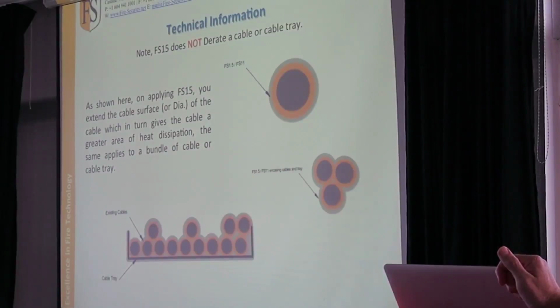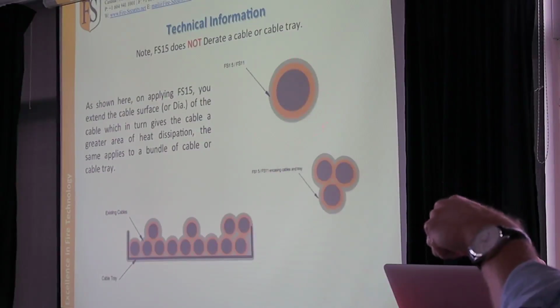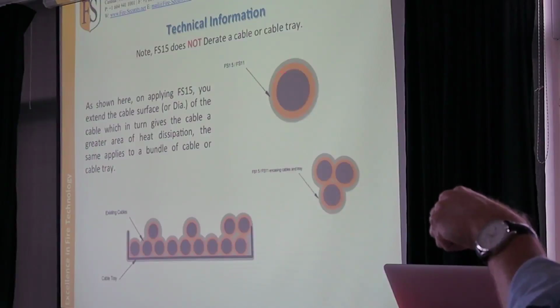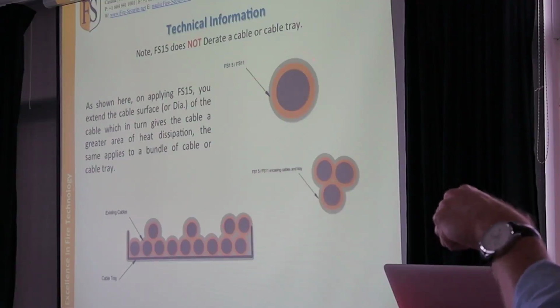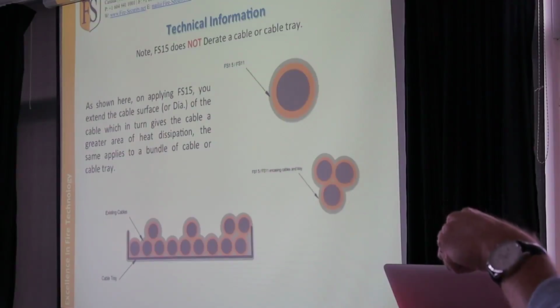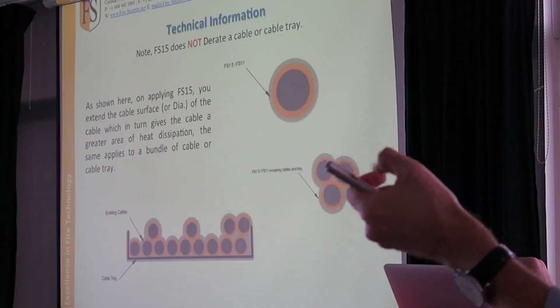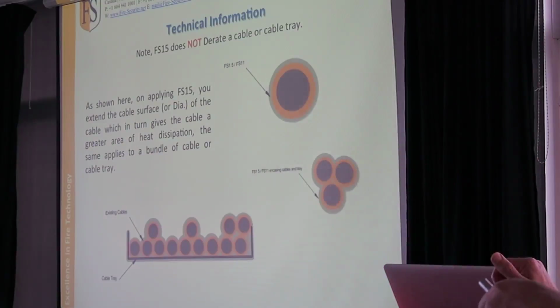So effectively what we do is that when the coating is applied to a cable surface, this is a non-insulating coating. So what you're doing is extending the cable surface itself, which gives the cable a greater area of heat dissipation. And what you'll see on the cable that was floating around, it's actually bumpy, it's not smooth. So in micro format, you're actually creating a greater area, so the surface area is again consumed. So we extend the cable surface or the diameter of the cable, which in turn gives the cable a greater area of heat dissipation, and the same applies to a bundle or a cable tray. You're still simply extending the surface.